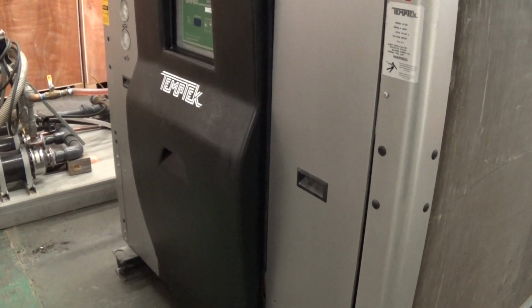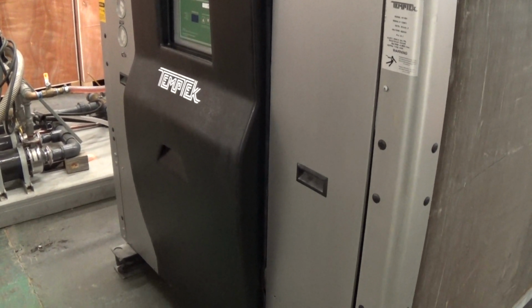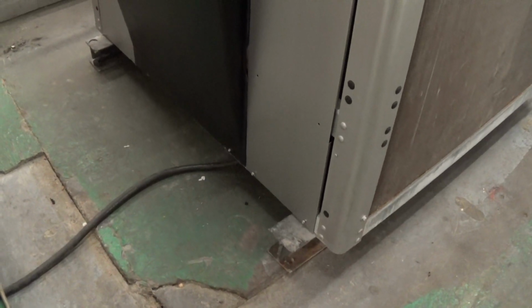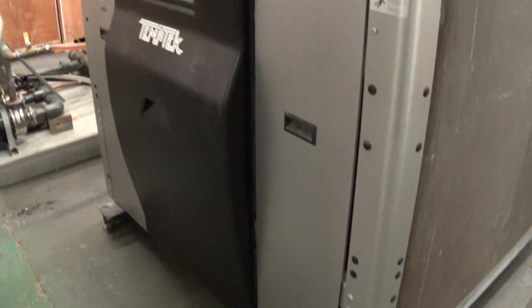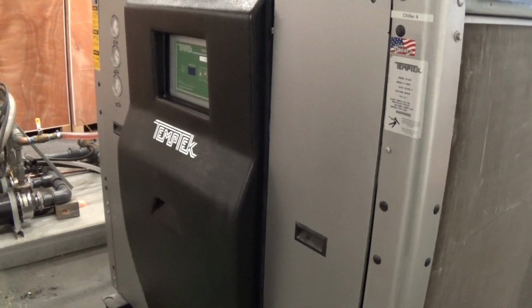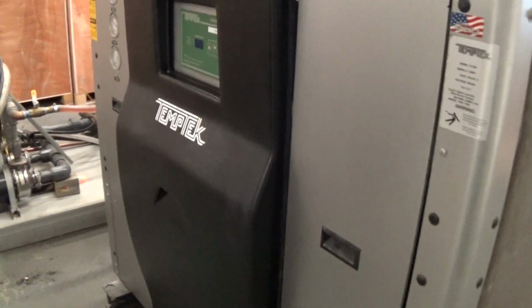If it's not, turn the power off at the chiller and your main disconnect, and change any 2 of the main incoming power leads coming into that terminal box inside the electrical enclosure area.